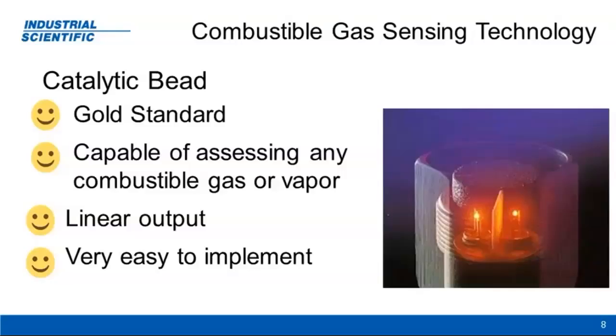Now, a lot of people might dispute that and say you can't detect vapors off hydrocarbon liquids, or heavier hydrocarbon vapors, with a catalytic bead sensor. I'd tell you that's not true at all. You can detect any combustible gas or vapor with this technology. The limitations come from the mechanics of the sensor, its construction, and filters that might be installed secondarily. But the technology itself is capable of detecting any combustible vapor. These sensors have a very linear output and are very easy to implement.